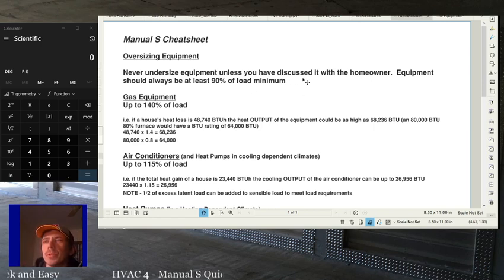But you should never really undersize unless they understand that it's not going to perform as well. The benefit to undersizing is obviously you're going to use less energy because it's smaller equipment, so they're going to have a lower bill the majority of days. Better than undersizing equipment is really using two-stage equipment or multi-stage equipment. That would be a better option than undersizing it. But if you want to go down, you can go down to 90% of load, but you can't ever go below 90% of load, and that's generally not recommended.